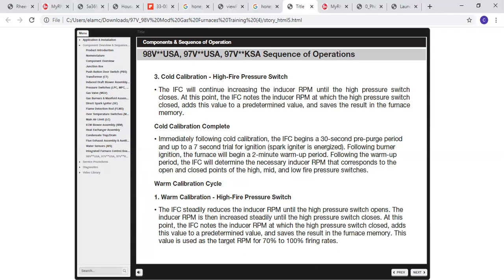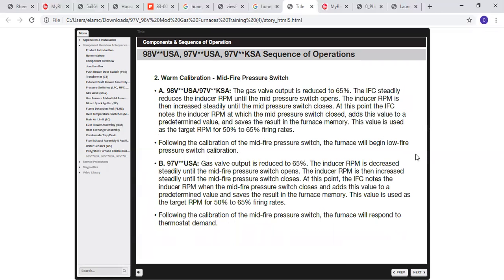Now your high fire pressure switch is going to be the RPMs for 70 to 100% firing rates. For the mid-level, there again, it's going to keep on reducing the inducer motor. The gas valve output is reduced to 65%. It keeps reducing until that mid pressure switch opens. At that point, the IFC notes the RPM value, saves that to the memory, and this value is used to target the RPMs between 50 and 65% firing rates.